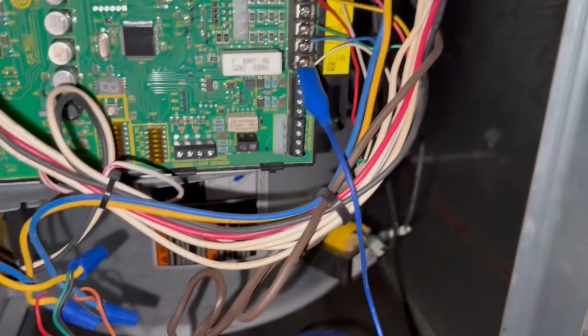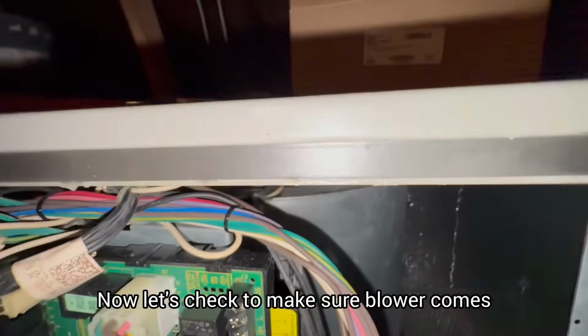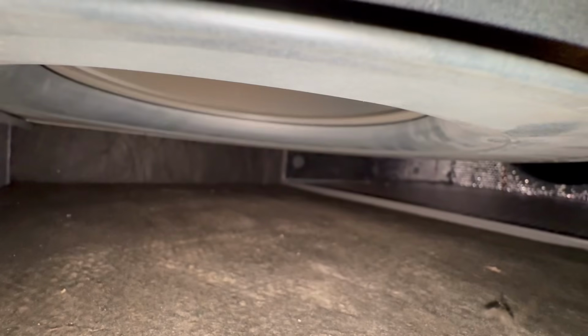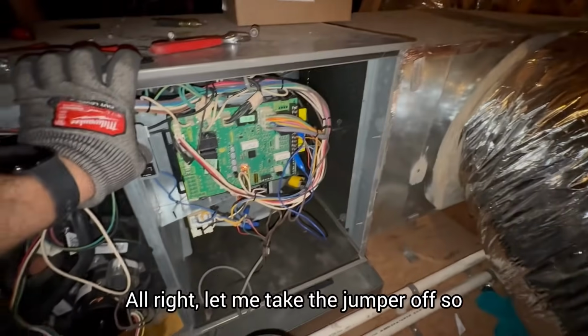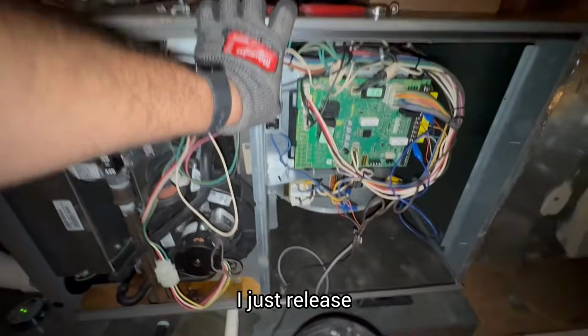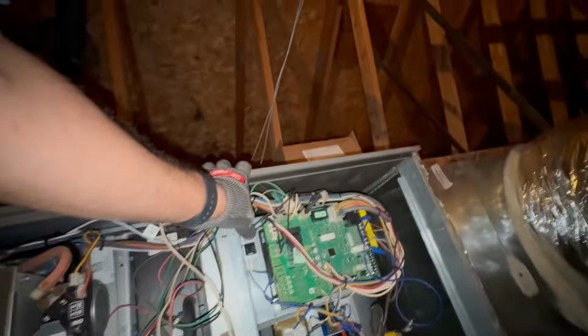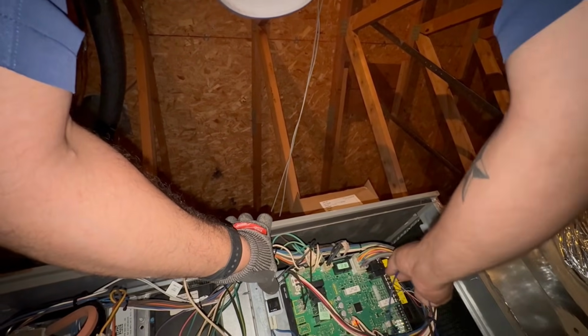Now for the moment of truth, let's go for this heating. Now let's check to make sure the blower comes on in a timely manner. There it goes. Let me take the jumper off so it'll cool down the heat exchanger before I release it. All right, took the jumper off, I'm gonna let it cool down.